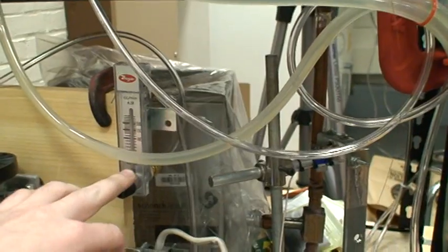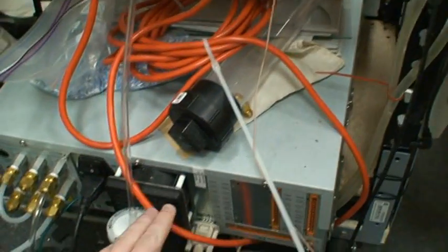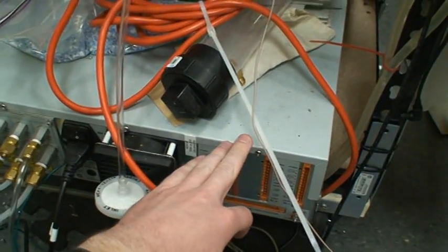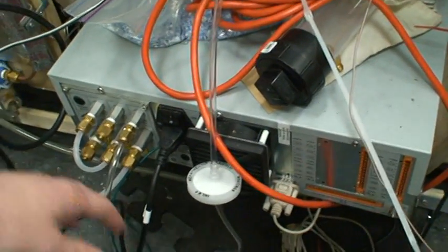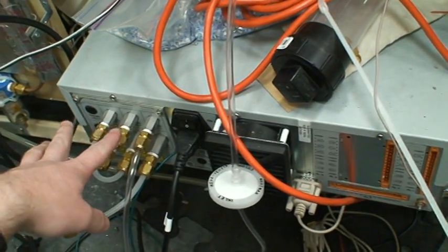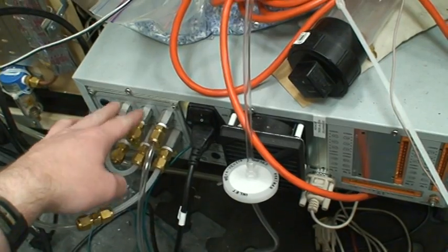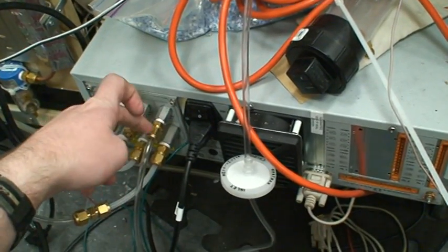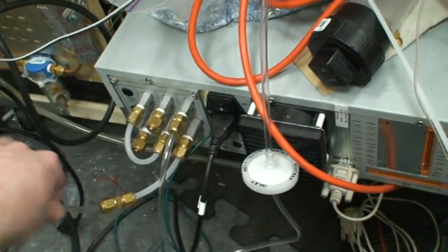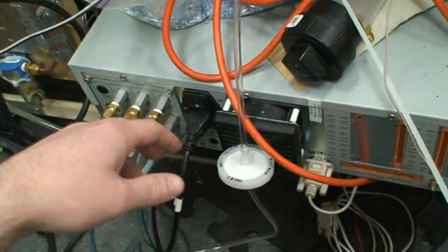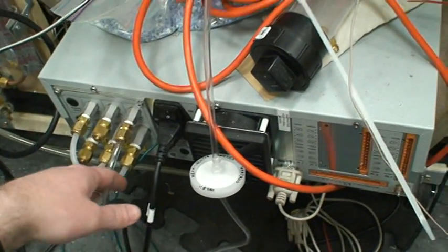So once our gas goes through this flow meter, it's going to go through a Servomex analyzer. So the Servomex analyzer is here. We can measure oxygen, CO, and CO2. Currently we're only measuring oxygen. Oxygen goes in through the sensor and then comes back out and into the hood return, so that we don't just vent it into the lab.